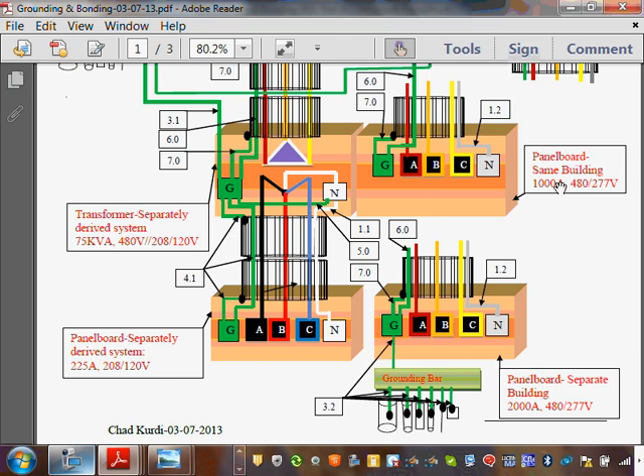Now your service disconnecting means is right there, and then up there you start going 4-wire conductor, right? 2 hots and a neutral and an equipment grounding conductor. Then you don't bond at the barn, but you still have to do what? At the barn, drive a ground rod, and tie. Does that make sense? The 3-wire and the 4-wire.